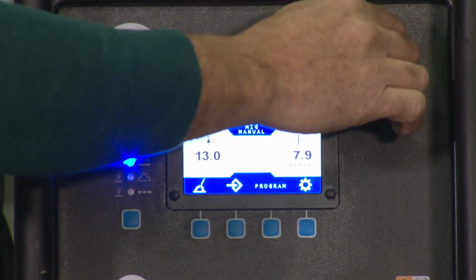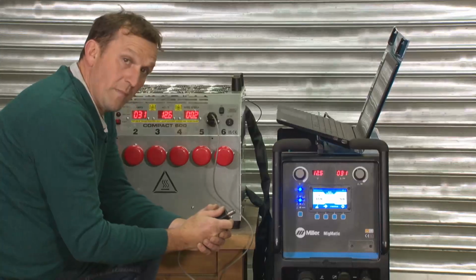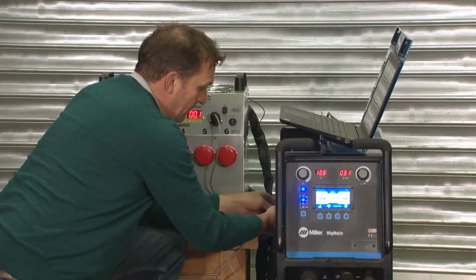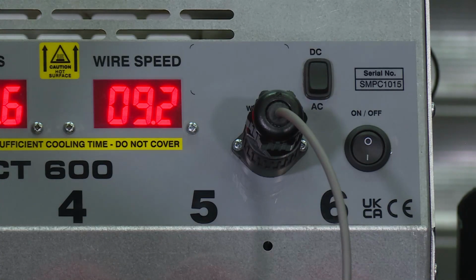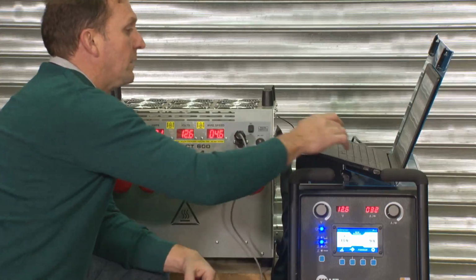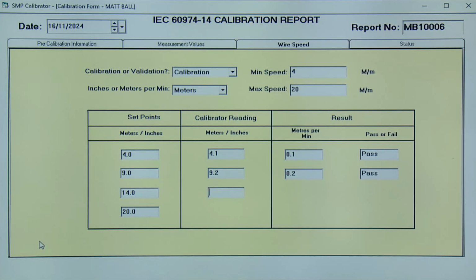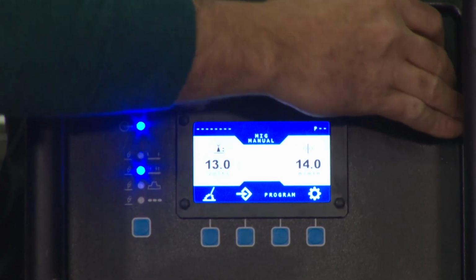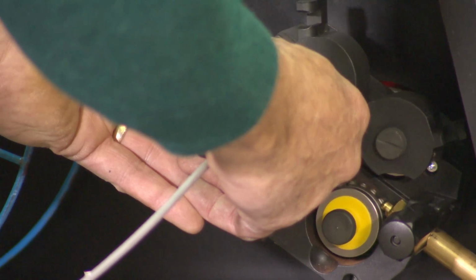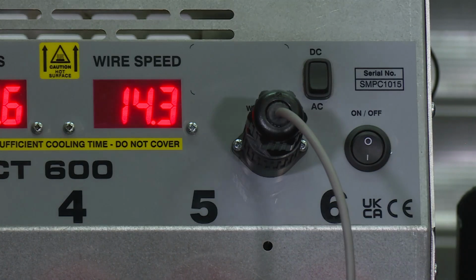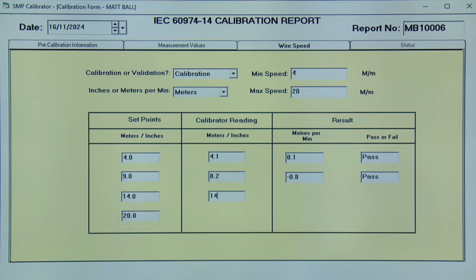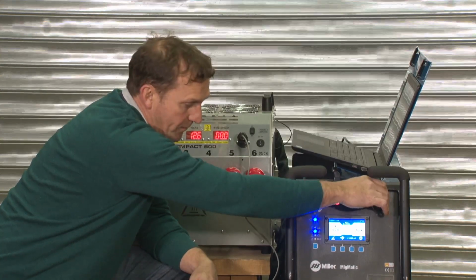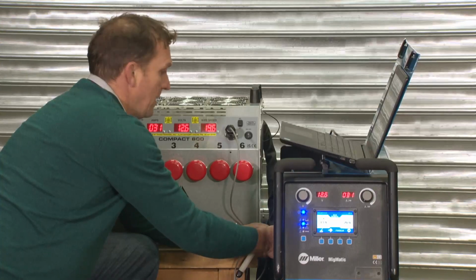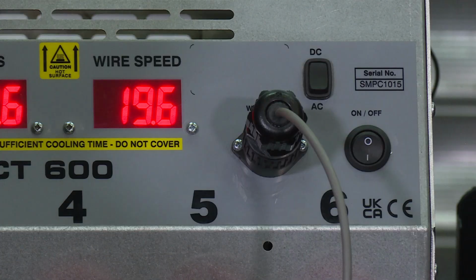On to our next reading at 9 meters per minute. And take our reading at 9 meters per minute. 9.2 meters per minute. Then our next reading, 14 meters per minute. We take our reading of 14.3 meters per minute. Then our final reading, 20 meters per minute. And our reading of 19.6 meters per minute.